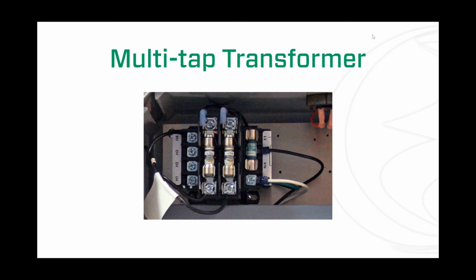Well, all of the components that we've talked about in our control panels anyway, typically operate on 115 volts. So again, it's very important if you have a multi-tap transformer in your control panel that you know what that incoming voltage really is and that you tap this multi-tap transformer on the correct terminal to get 115 volts out of it. If you don't get it tapped correctly, if you just assume that you know and tap it to what you think and it's not right, you will damage components inside of the control panel. And again, the only way you're going to be able to fix that is by purchasing and replacing parts in the control panel, not the way you want to learn.